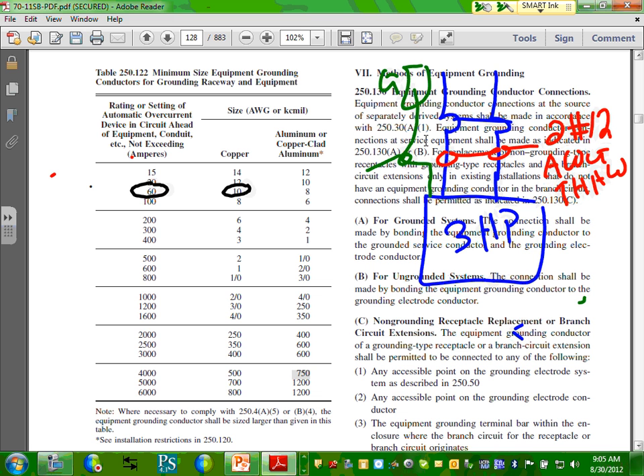Based on this table, what's the size? Number 10. What's the ungrounded conductor? Number 12. In the motor section, it says the equipment grounding conductor is not required to be larger than the ungrounded conductor. One more time, this is typically for motors. The equipment grounding conductor does not need to be larger than the ungrounded conductor. So yes, we came up with 10, but we default to what? To number 12 as a minimum. Why? Because the ungrounded conductors are number 12.